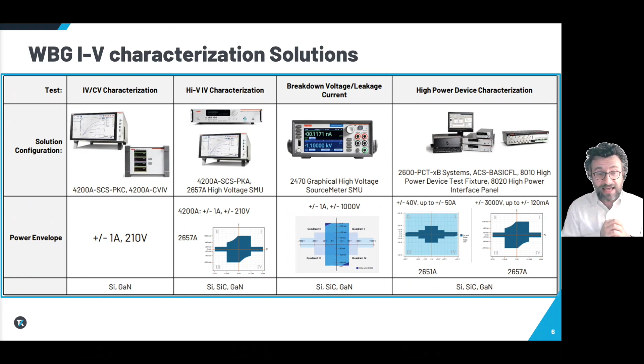These and a lot of other capabilities impact the requirements for proving the reliability of the power electronic devices. So the reliability tests really involve stressing batches of sample devices for hundreds or thousands of hours with ratings that are beyond the normal operating voltages and temperatures. During this stress, a variety of operating parameters are measured at a specific time interval, logged, and saved in long recording data logging for further data analysis and statistical evaluation. Here we're talking about tests like the HTOL, the HTRB or the HTFB. These tests need to use a continuous bias sometimes, such as a fixed voltage, or sometimes a staircase ramp, or they have a cycled bias that applies a duty cycle, or a bias voltage is changed at a certain frequency.